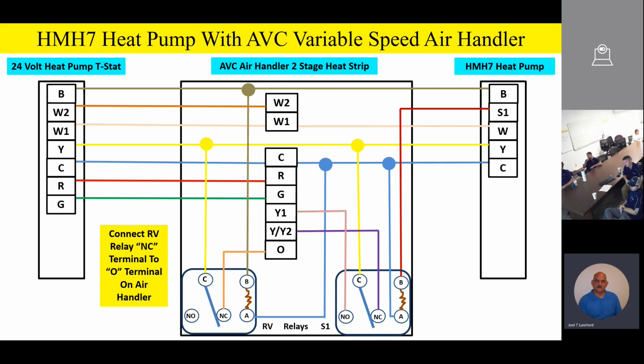So on the variable speed product, here's why we have that RV relay. On a heat pump, we have to tell the indoor unit when it's in the cooling mode of operation. This drives some advanced functions like some of your cooling on delay and some of your fan relay operations. In addition, it also drives some dehumidification functions on the variable speed product. So the bottom line is in the cooling mode of operation, we need 24 volts on that O terminal on the variable speed air handler or the variable speed furnace to tell it it's in the cooling mode of operation for some advanced cooling dehumidification functions. And so we're going to utilize that RV relay to feed 24 volts to the O terminal on the variable speed products for some advanced functions.